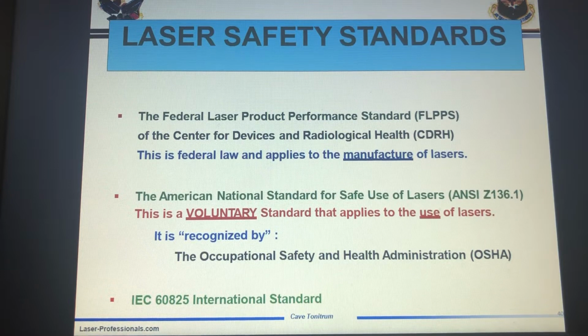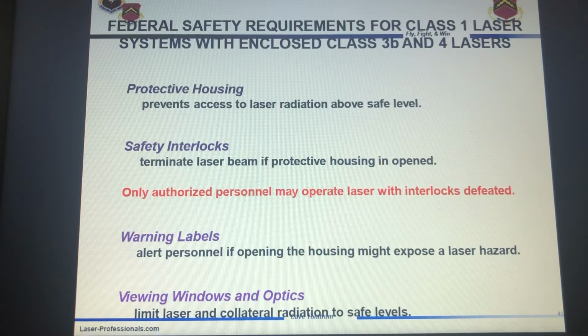Just like I said, the standards that we follow, the FDA as well as ANSI, govern how we use these particular products, and we follow them all. Some things for our lasers that keep us safe are a protective housing, safety interlocks, a passcode, warning labels, everything you can think of so that we do not damage ourselves and or the patient.